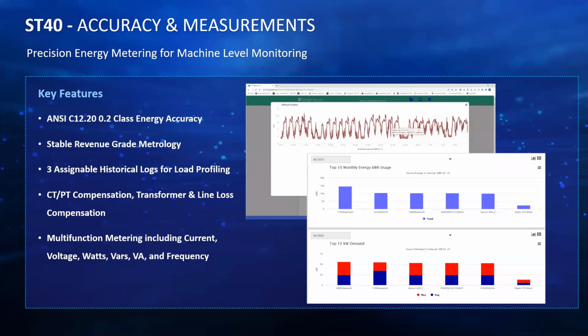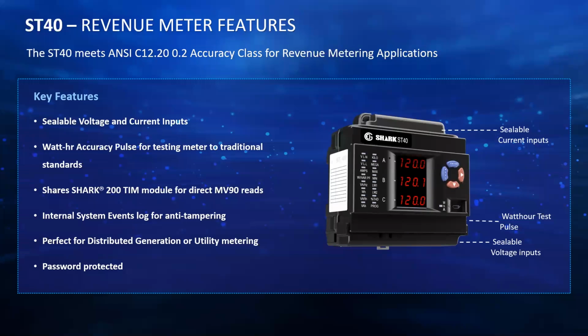In addition to monitoring energy, we also give you current, voltage, power, including watts, VARs, VA, frequency, and power factor. Revenue features for anti-tampering: the current inputs and the voltage inputs both have seals. So you can put a revenue lock on the meter. If anyone did get in to change the wiring of the meter, they would have to break that seal and they would have to put a new seal on. So if there were any issues, you would be able to see if someone did get in and make a physical change to this meter.